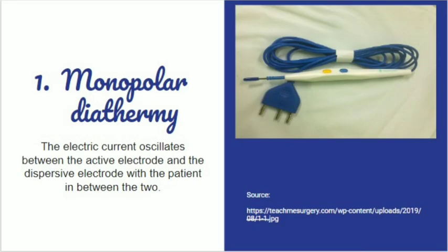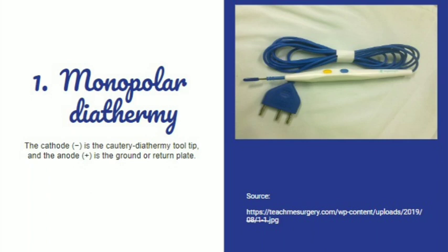First we will discuss monopolar diathermy. Monopolar means one active pole; the other is a ground or dispersive medium where the electricity goes to disperse. The electric current oscillates between the active electrode and the dispersive electrode with the patient in between. As you can see in the figure, there is only one tool tip — the cathode, the active electrode. The other is the ground plate, or dispersive plate, that acts as the anode.